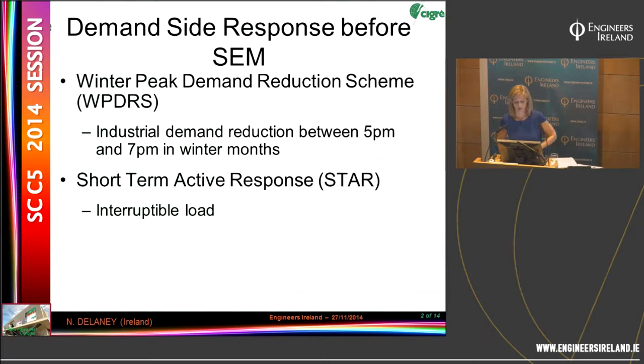Short-term active response, STAR, is an interruptible load type scheme which is still running. It's been running for over 20 years. And basically customers are contracted to make some of their load or all of their load available for interruption. The sites are fitted with under-frequency relays, and if there's a generator trip on the system and the frequency drops down to a certain level, then the load will be disconnected. So there's currently 45 megawatts of load contracted under STAR, and that provides reserves to the system operator.